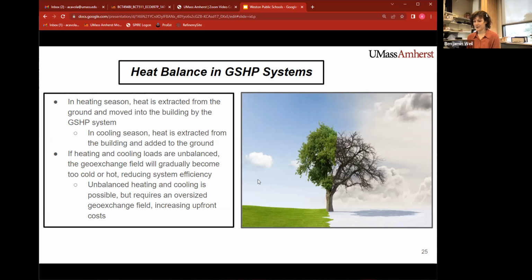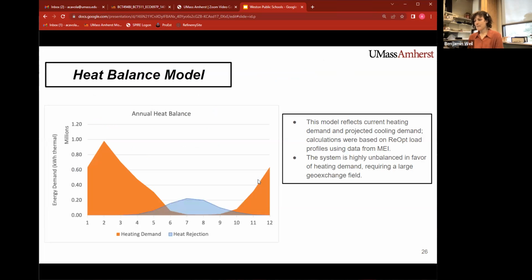So the less heat the system has available to extract in heating mode, which is more of a concern in this heating dominant climate, the harder it has to work, and this reduces its overall coefficient of performance. So this model reflects current heating demand and projected cooling demand. Calculations are based on REopt load profiles using data from Mass Energy Insight. And as you can see from this graph, the system is highly unbalanced in favor of heating demand and would require a very large geoexchange field, i.e. the system would extract a lot more heat than it adds.